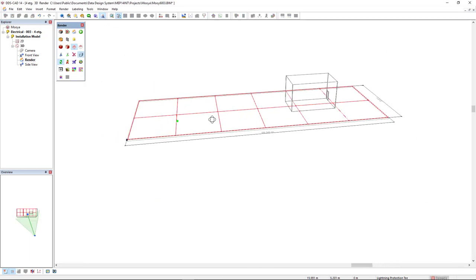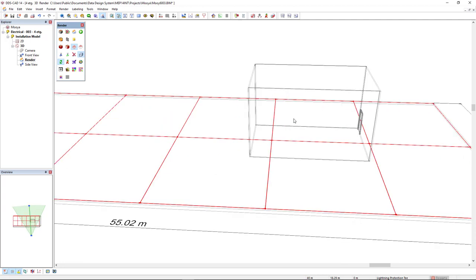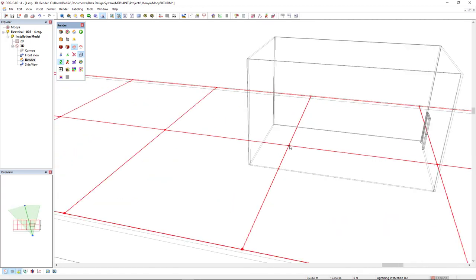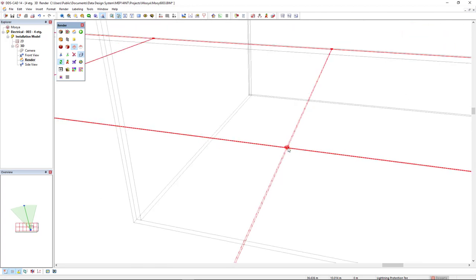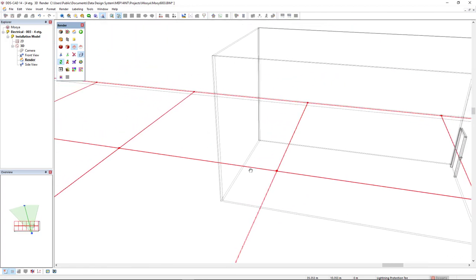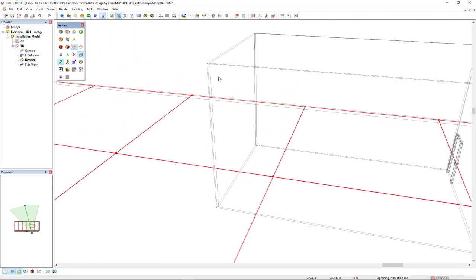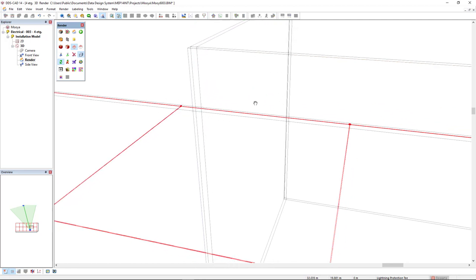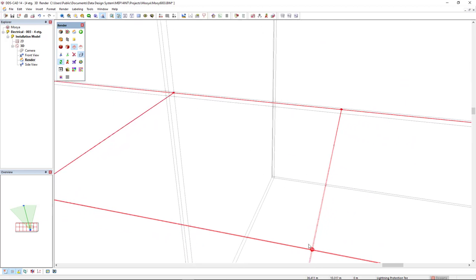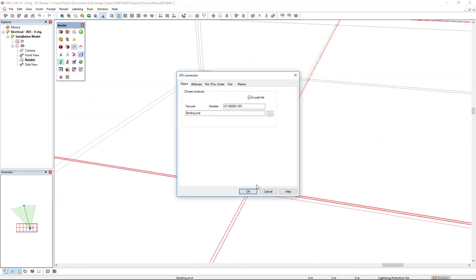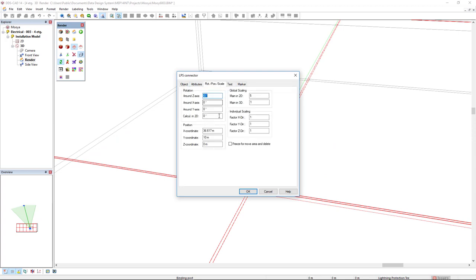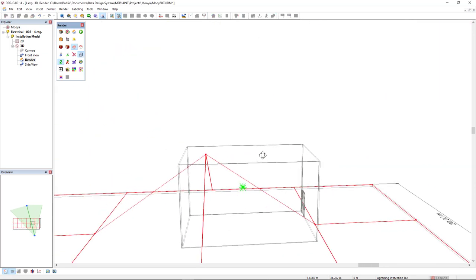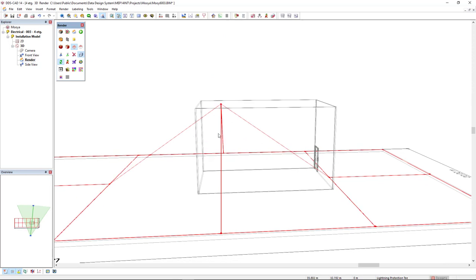Okay the grid is good but we see here that with this area here this binding post should be on top. If I press and hold shift over this end point we see that the third coordinate is 6.13. So the height of this knot is 6.13. What I will do, I will double click this binding post and in the tab Rot./Pos./Scale I will change the z coordinate to 6.13. Zoom out we see that we created a pyramid geometry with these conductors. I will fix this.